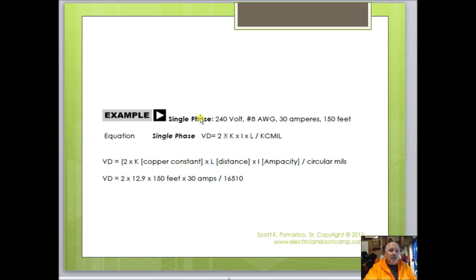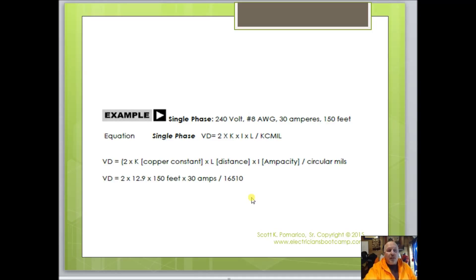Let's look at a problem: 240-volt, number 8 wire, 30 amps, at 150 feet. The formula is VD = 2 × K × I × L ÷ circular mills. Filling it in: 2 × 12.9 × 150 × 30, divided by 16,510. You can pause the video to work out that answer, then we'll move on.